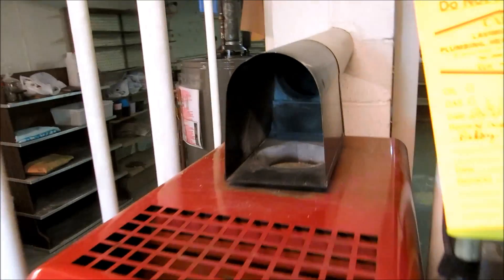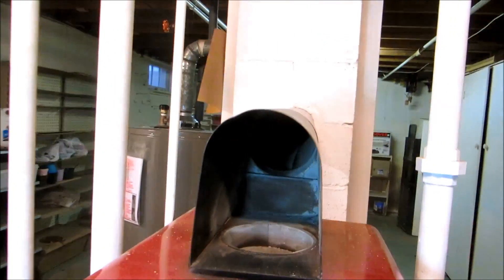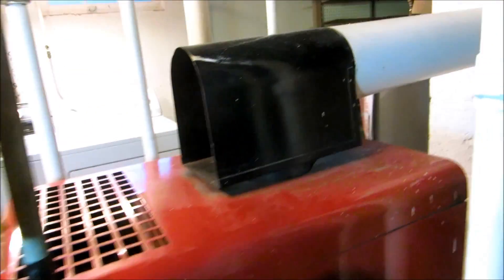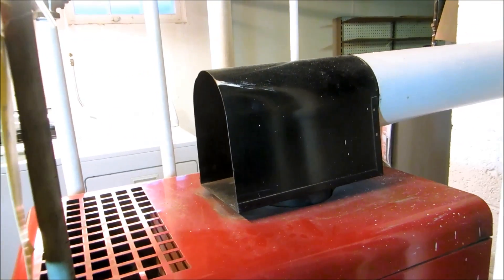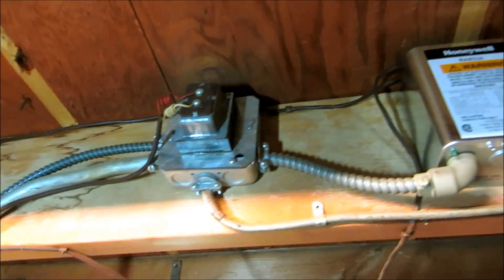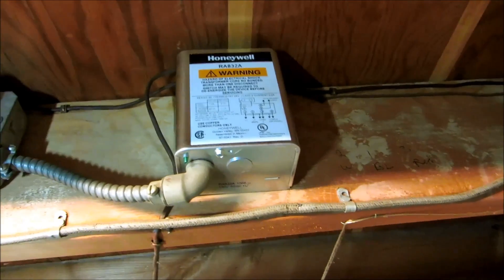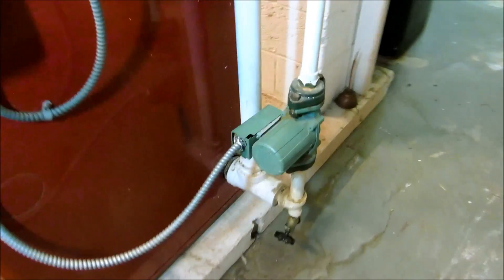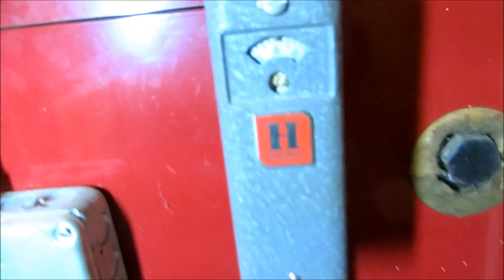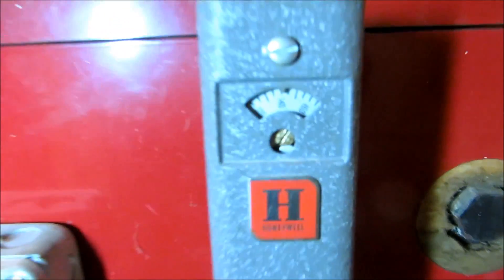Look at this old boy — look at this draft hood, that's something. It was a no-heat call. I changed that switching relay up there — that switching relay turns that circulator on, which wasn't working. There's a circulator control here set for 140, so the boiler's going to fire to 140.